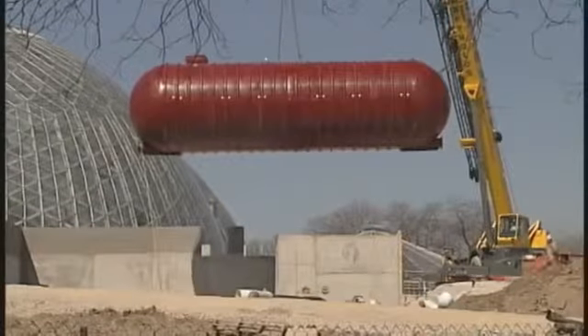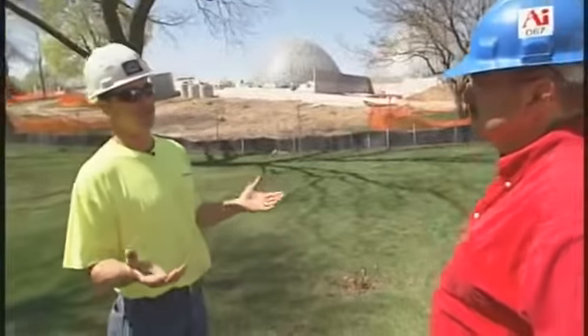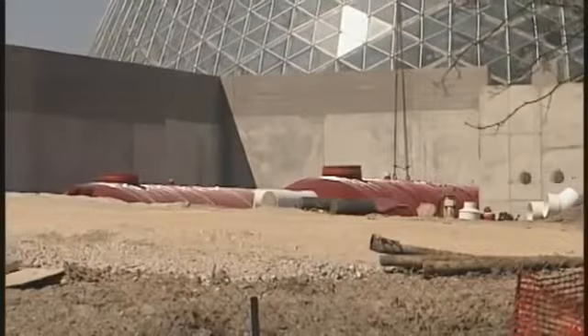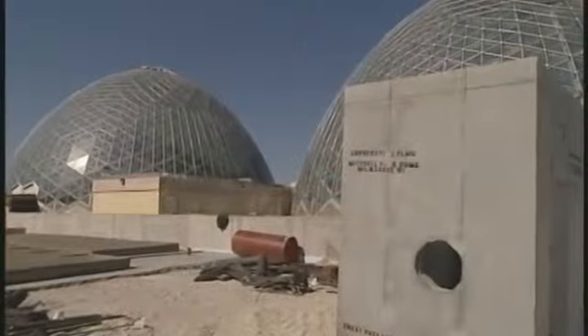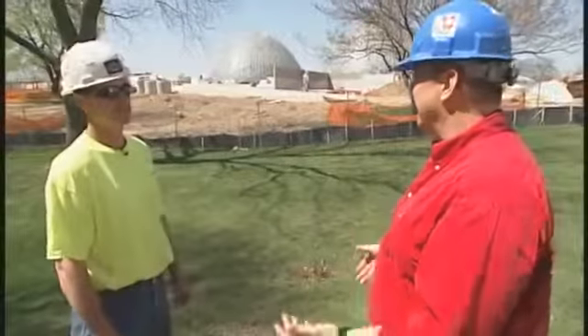So at the end of the day, how does the water get from those tanks into the buildings? Well, they're all manifolded together, so as the water comes in from the drains, the tanks will fill up evenly, and then the head pressure itself will flow into the wet well, and then there's a submersible pump with floats that'll activate to force it into the building. And then it's just part of the piping system once it gets inside. And again, it's using water that is just falling from the sky. You're reclaiming it. Doesn't get any better than that.